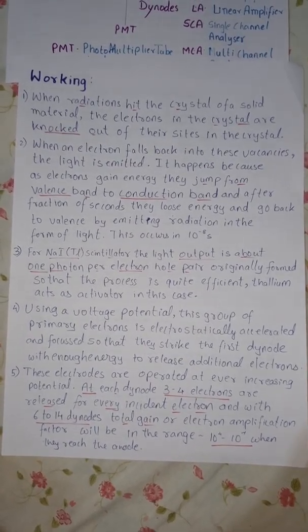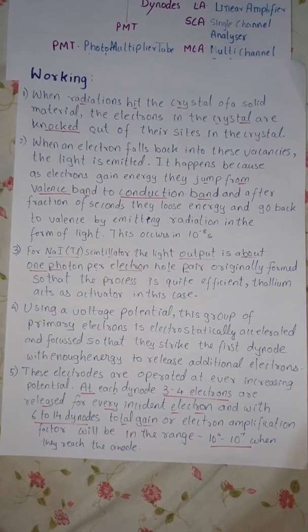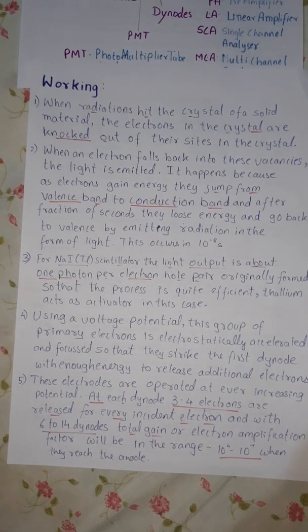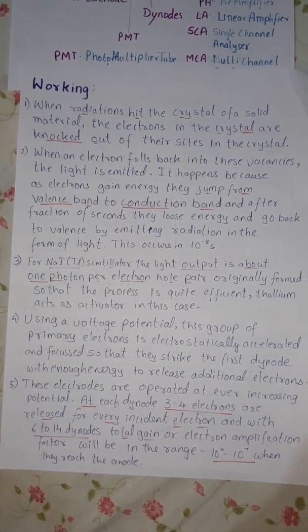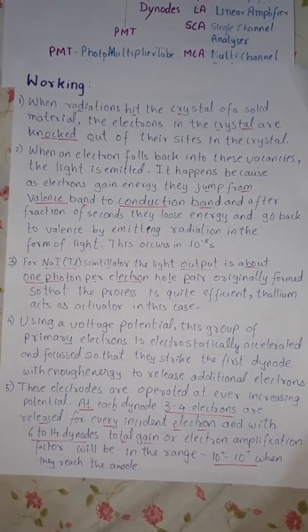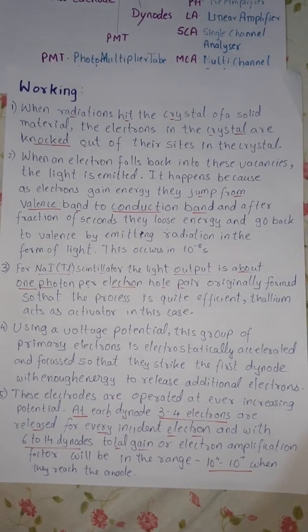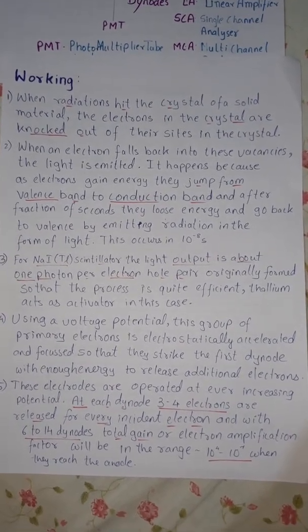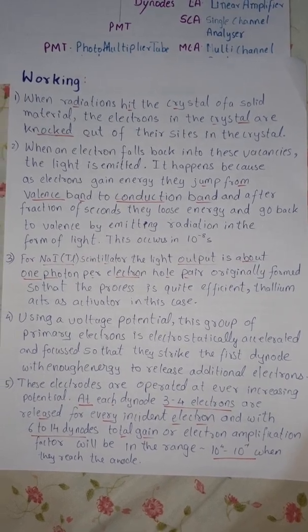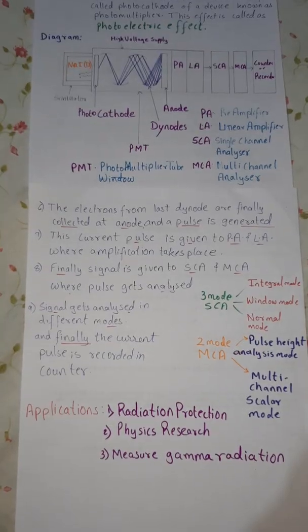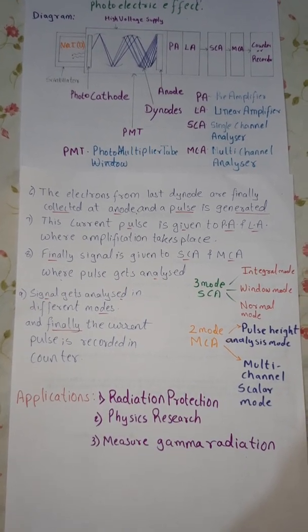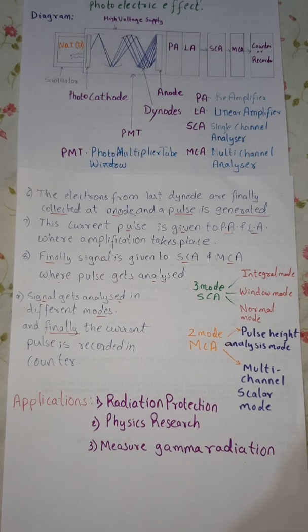These electrons are operated at ever-increasing potential. At each dynode, 3 to 4 electrons are released for every incident electron and with 6 to 14 dynodes, total gain or electron amplification factor will be in the range of 10 raised to 4 to 10 raised to 7 when they reach the anode.